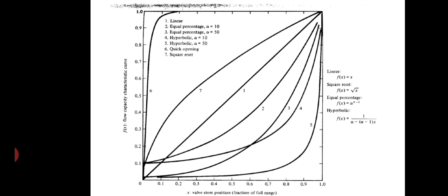Okay, the equal percentage valve, or this characteristic, is the most commonly used valve in the process industries. The concept of this is the change in the flow per unit valve stroke. We will see these things from the mathematical expression also, but here we will just try to elaborate from the definition. The change in flow, listen very carefully to what I'm telling you, the change in flow per unit of valve stroke is directly proportional to the flow occurring just before the change is made.